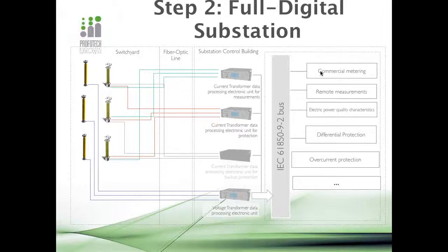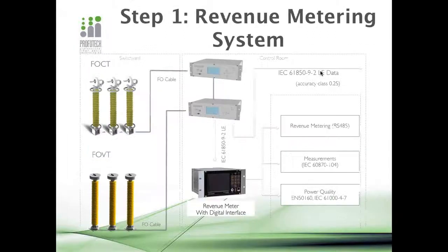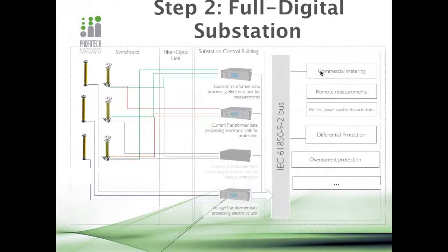We can monitor power quality in accordance with the IEC and EN standards. Step 2 is a fully digital substation, when we use not only metering but all the protection schemes and automation. Everything is built based on the digital process bus, the IEC 61850-9-2. So in this case, if I go back and refer to this slide, you can see that we have only 2 electronic modules installed. One is for the current transformer, the second one is for the voltage transformer.